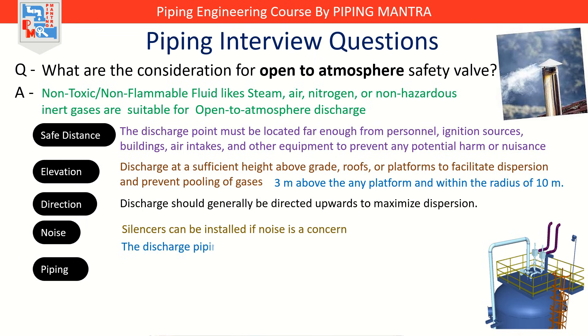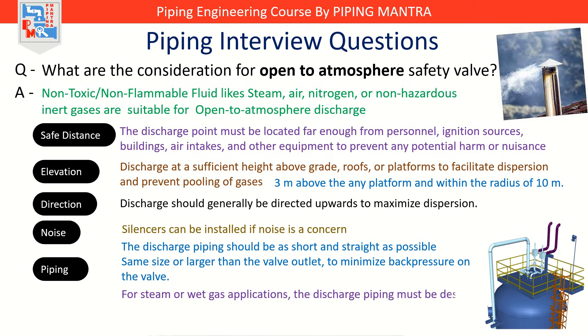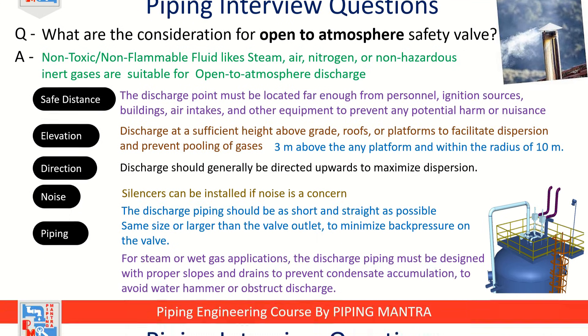The discharge piping should be as short and straight as possible — typically the same size or larger than the valve outlet to minimize back pressure on the valve, which can affect its opening characteristics and capacity. For steam or wet gas applications, the discharge piping must be designed with proper slopes and drains to prevent condensate accumulation, which could lead to water hammer or obstruct discharge.